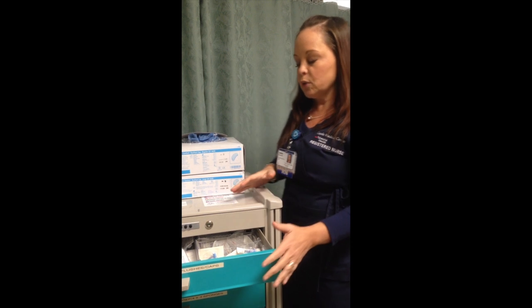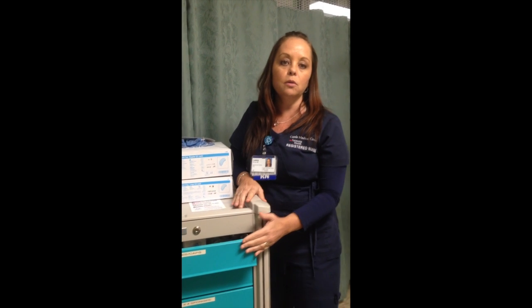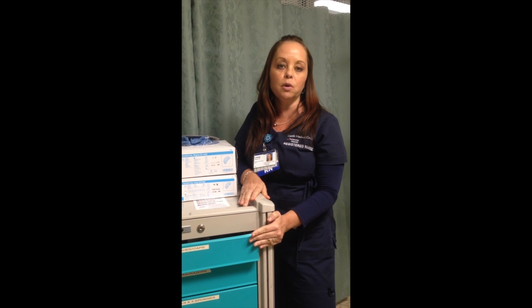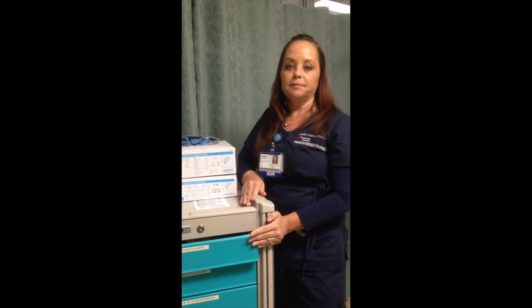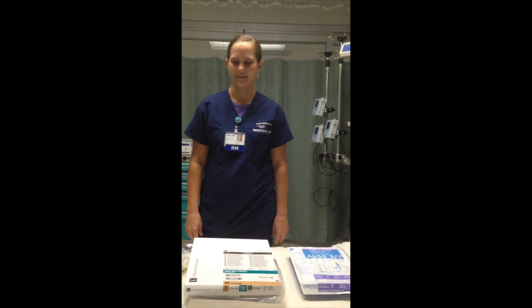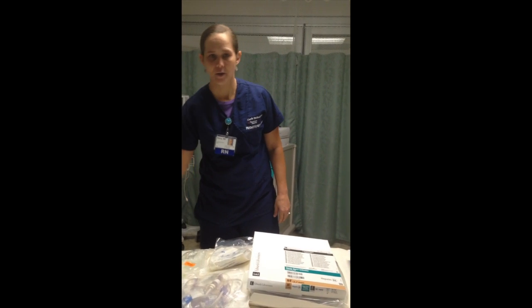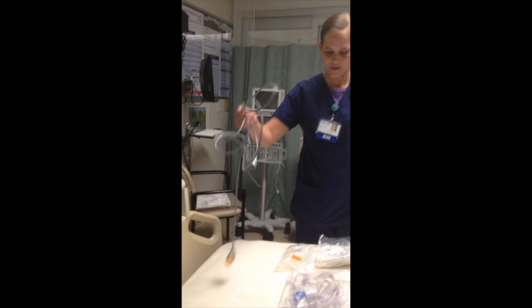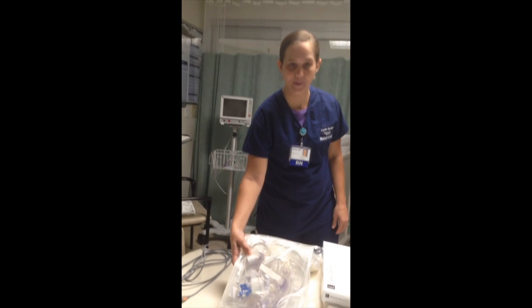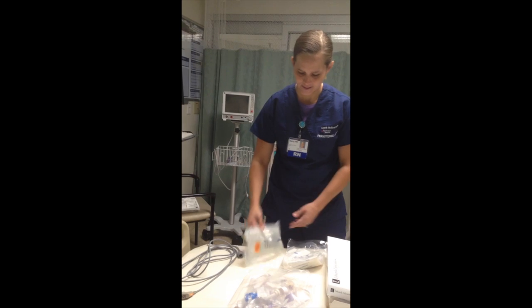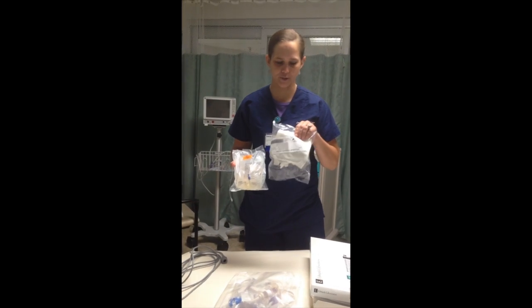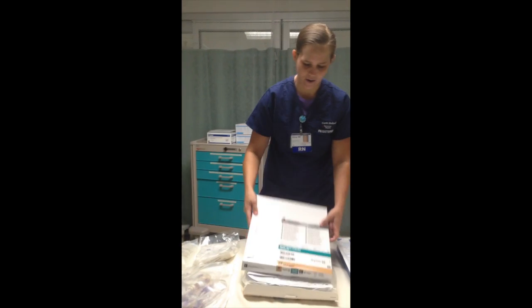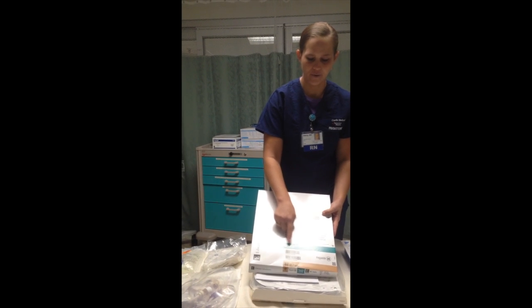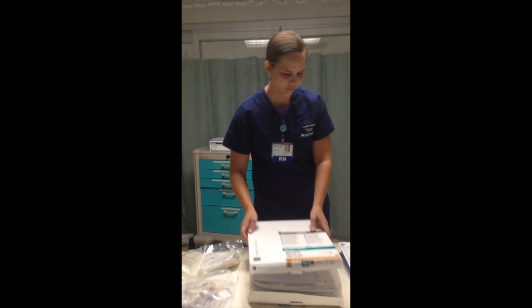The next portion of this video, Darcy's going to go through setting up your pressure cables and your lines. I'm going to be going over the equipment you're going to need to set up the Swan Ganz. The first thing you'll need to grab is 3 pressure cables. You'll also need the bifurcated pressure tubing, a 500cc bag of saline, and a pressure bag. You'll need your Swan Ganz, and you need to make sure it's the CCO. This is an 8 French that we carry.